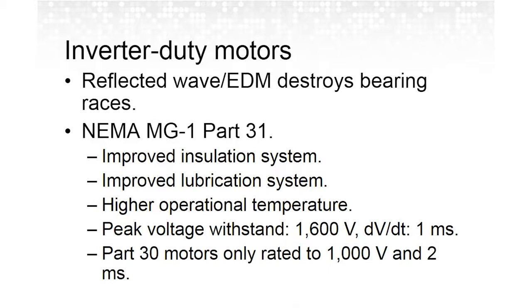What happened? The key to remember is that although any general purpose AC induction motor can run off a VFD, the big concern is how long it will last while connected to a VFD. The biggest concern that we have is called the reflected wave phenomenon, or electro-discharge machining, that destroys the bearing races in the motor that are at both ends of the shaft.